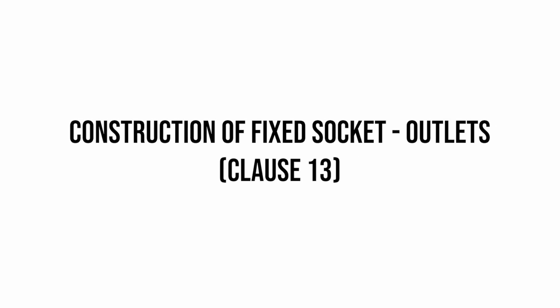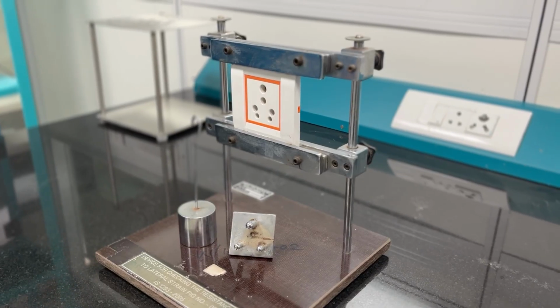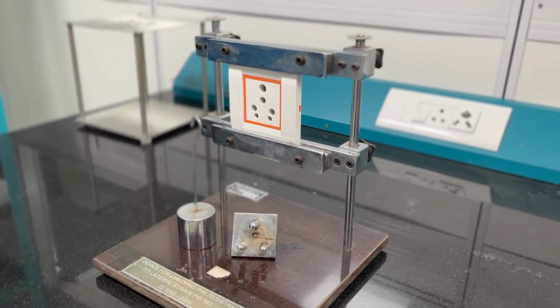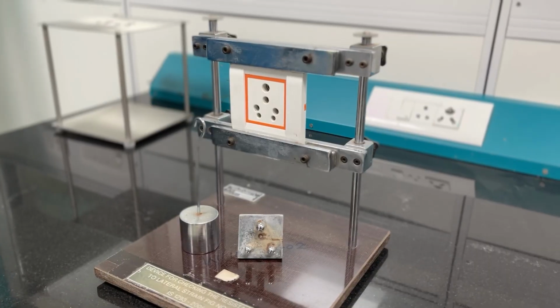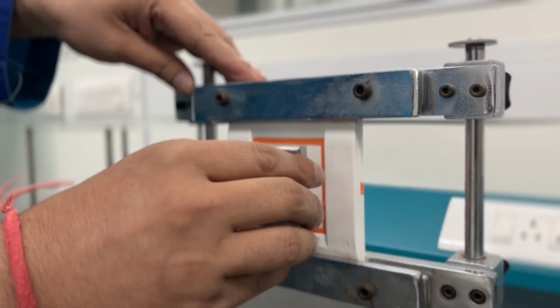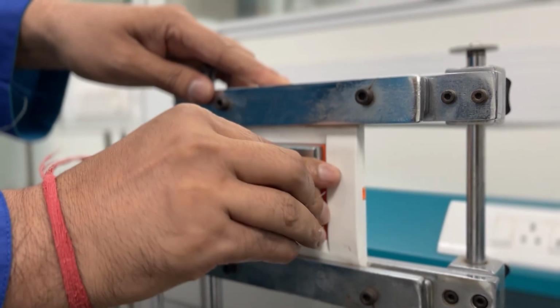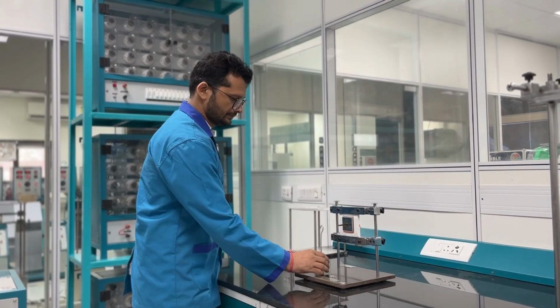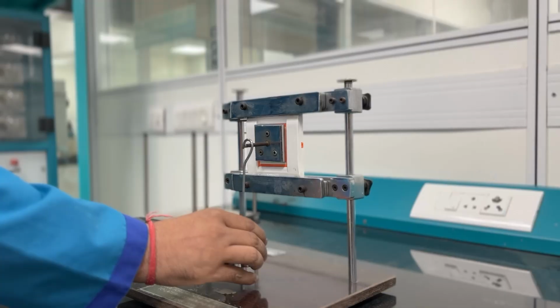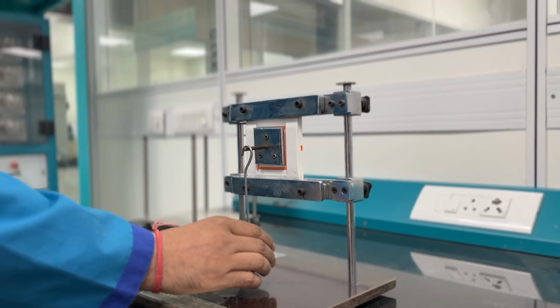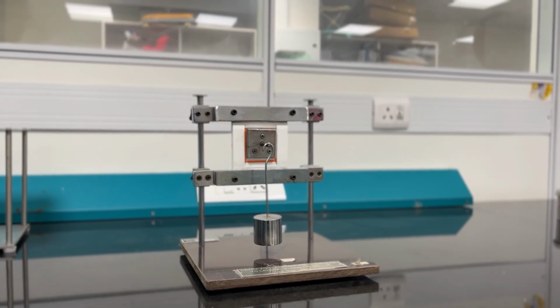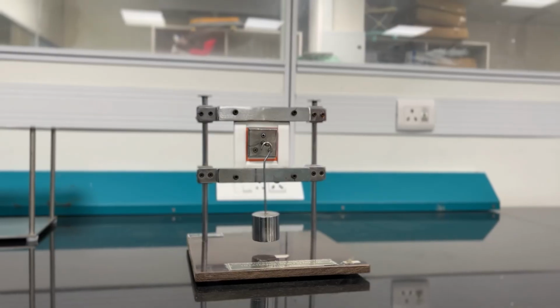Construction of fixed socket outlets. Clause 13. The socket contact assemblies are examined for sufficient resiliency to ensure adequate contact pressure on the plug pins. It is verified that metallic contact is established on at least 2 sides of the pin when fully inserted.